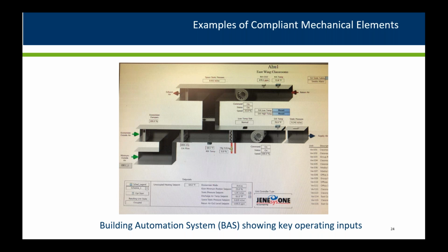Here we have an example of a building automation system screenshot showing a diagram of a VAV air handling unit at current operating conditions, demonstrating a number of code elements that are being complied with. First, we see that the economizer is present and active, and also the unit controls include optimal start, supply air temperature reset, and static pressure reset capabilities. Minimum outside air is brought in through ERU-1, and the name suggests that it is an energy recovery unit. The heating setback is also noted here.